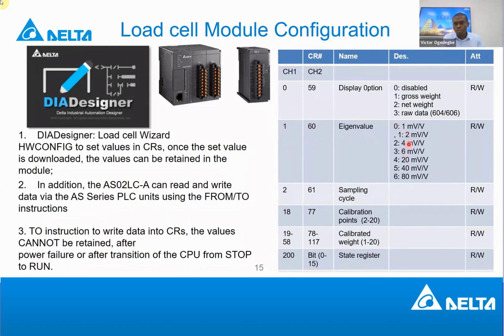You see the eigenvalue also for each channel. Depending on the specification of the sensor you have chosen, you choose the correct eigenvalue. You can use this API to tell the module, for the sensor you are measuring, this is the eigenvalue, and then reconcile that with the signal coming from the load sensor. Then you also have the sampling cycle, which is also very important. The control register is 2 for channel 1, and for channel 2, the control register is 61. So you can set different times. I think the maximum time we saw on the other page is 400 milliseconds. The bigger the time, the more stable your measurement is likely to be. Then you also have registers you use for calibration.